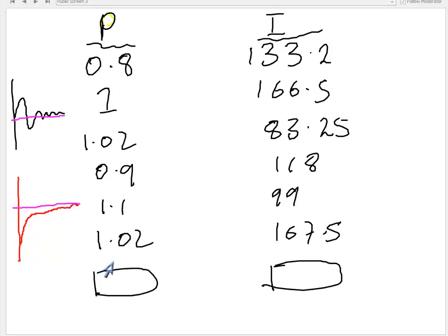In actual fact, the values that we calculate using the open loop bump method are just a starting point. What we're supposed to do is use those just as an indicator so that we know roughly where the P term really is. If you've calculated your P term to be roughly 1, then you know that it's somewhere between 0.2 and 4.